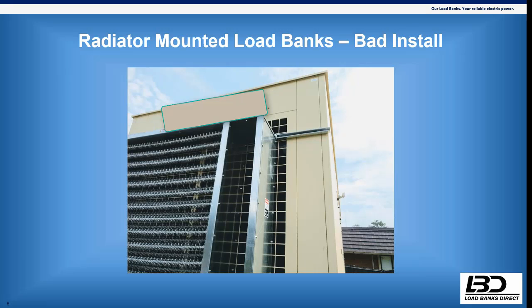I thought that was a good example to throw in here of what not to do. That is a really good picture. Hanging it on the outside of the enclosure is a solution, but it's not always the best solution. You look at this and there are a lot of things wrong with it. And from an aesthetics point, it just doesn't look clean. The right thing to do is try to put it inside the enclosure.